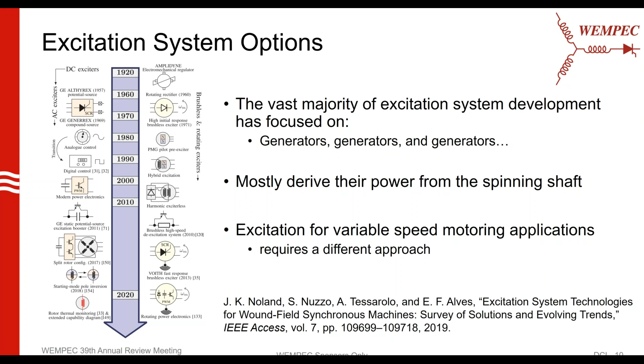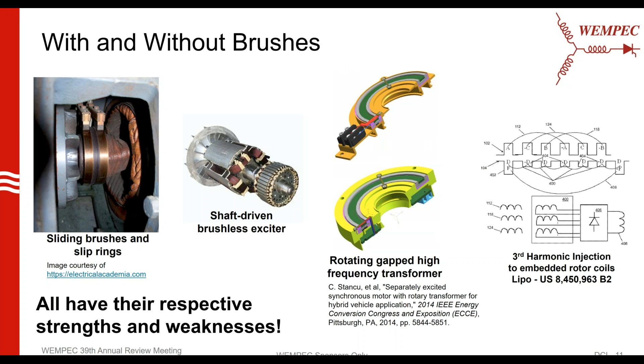Good, so with and without brushes. These are some of the more common options. Obviously on the left you have brushes and slip rings, and this goes back to the beginning of time of electric machines. You also have shaft-driven brushless exciters, which is another machine located on the shaft, which is then coupled to the main field winding. You then have rotating gapped high frequency transformers. This is just a ferrite transformer that has its primary and secondary windings free to rotate, but there's a small air gap in there that allows them to do that. And lastly, a third harmonic injection to the rotor coils. This is actually an invention of the recently deceased Professor Lipo, but we'll talk about that.